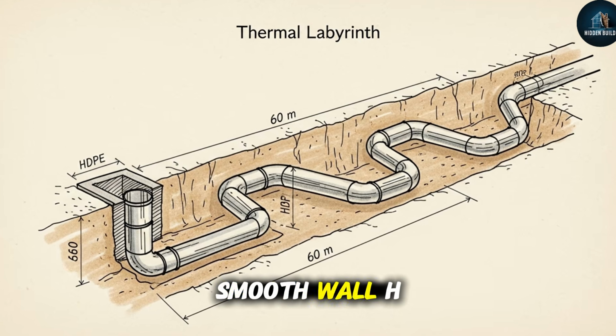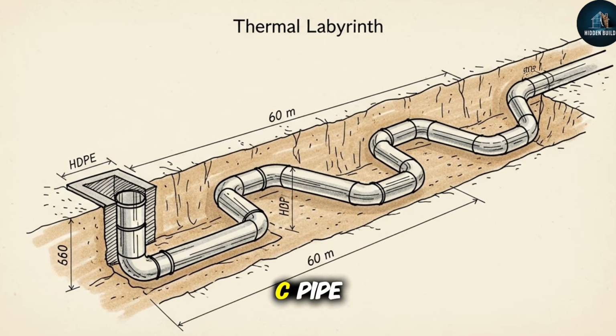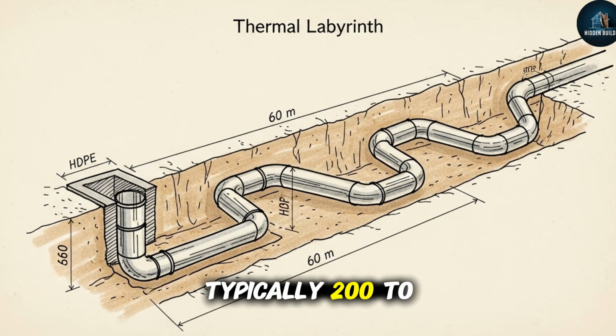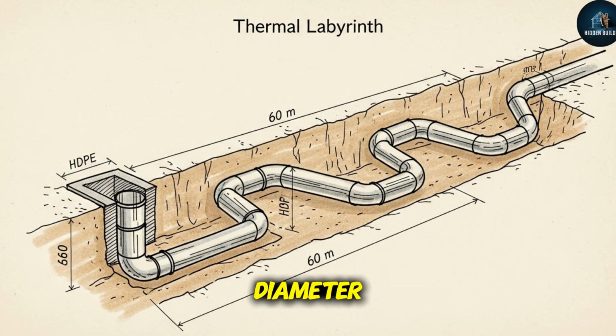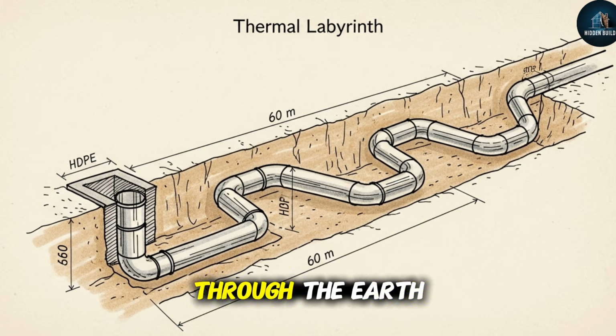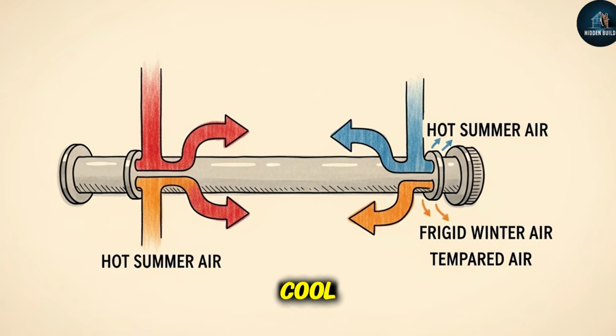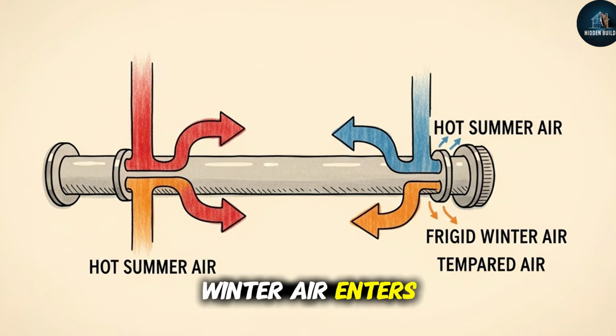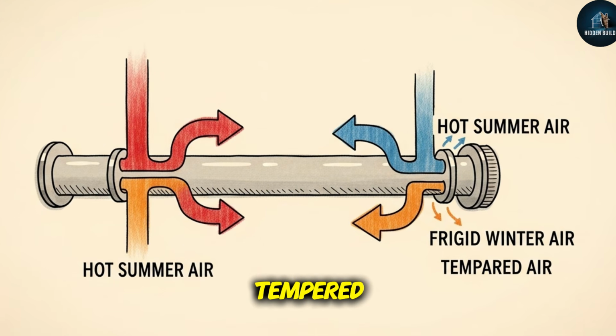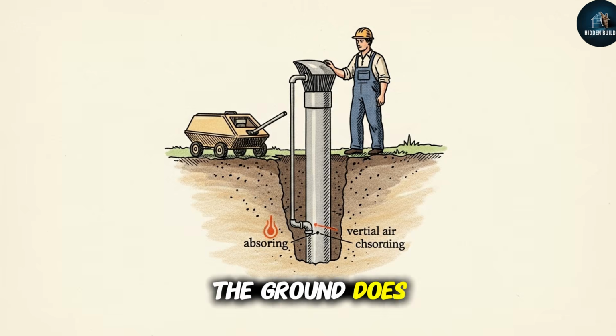You bury a smooth-wall HDPE or PVC pipe, typically 200 to 300 millimeters in diameter, and run it 30 to 60 meters through the earth. Summer air enters hot and exits cool. Winter air enters frigid and exits tempered. The ground does the work. You just built the pathway.